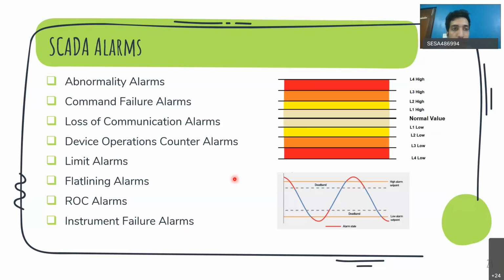Some different types of alarms I have listed here. Abnormality alarms. Normally all your devices will be in some state, and because of some abnormality, they move into an abnormal state. So for example, your circuit breaker is normally closed, but because of a fault, it gets tripped and abnormally becomes open. Okay. Similarly, your earth switch is normally open, but when you want to ground a particular section, it is closed. So that is an abnormal condition. So whenever any device in the network moves into its abnormal state, an alarm will get generated. So that is one type.